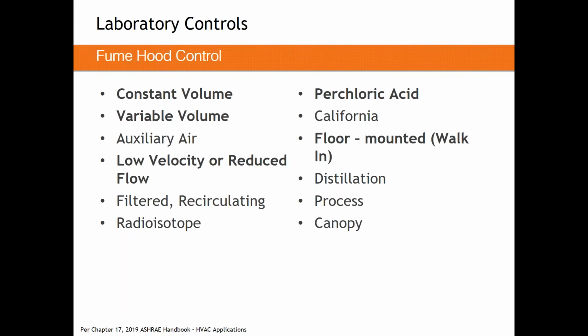Now, fume hoods are really what make a lab a lab. They're what make wet labs a little bit complicated. And this is what's going to drive you to a certain style of valve over the other, because fume hoods are really the most important piece of equipment in a laboratory, oftentimes. Fume hoods are what we call the primary engineering control, meaning if the fume hood is doing its job and it's being used properly by the user, we should be doing a pretty good job of containment in that space.